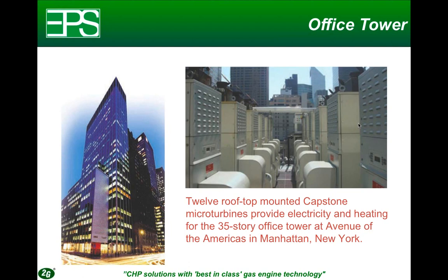Microturbines, because they have less noise and vibration to deal with, are especially well suited to be installed at higher levels in buildings. Reciprocating engines have a bit more vibration to contend with, and as you get higher up in buildings, it gets trickier to make sure no nuisance noise and vibration is transmitted to the building. So for high rises, higher buildings, microturbines may well be a better fit for this type of application.